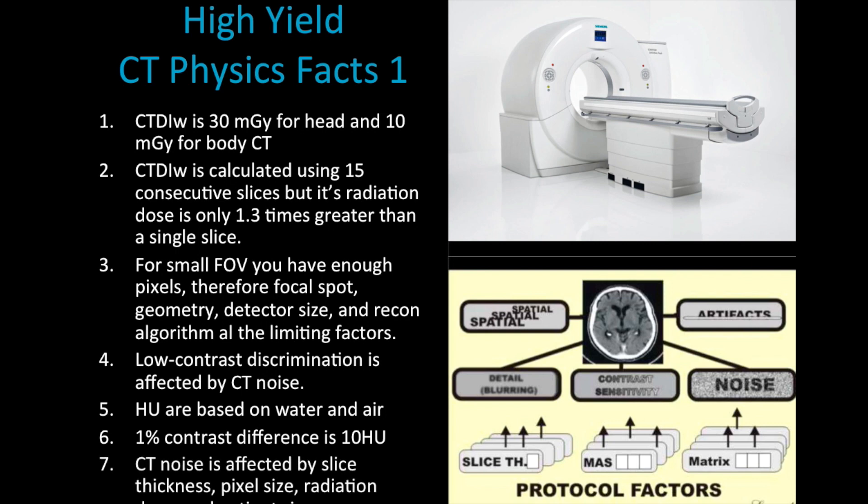Hounsfield units, as you might know, are based on the measurements of water and air. We normalize water to represent a value of zero Hounsfield units and air represents a value of minus one thousand. One percent contrast difference is equivalent to ten Hounsfield units, and that's just a fact you should know. So every time you see a ten or twenty difference in Hounsfield units, you know you're dealing with one or two percent contrast difference.